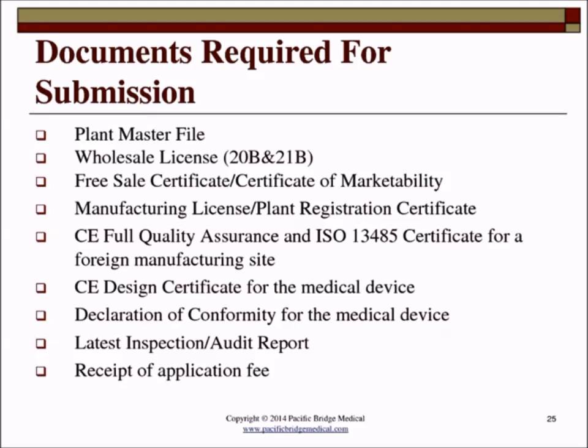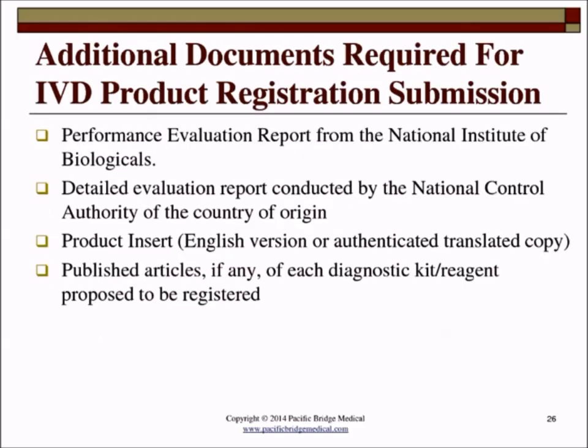Here again are some more things in the documents to be submitted. The following additional documents are required for notified diagnostic kits. Beyond what we said in the last couple of slides for devices, if you have diagnostic kits, you have to provide some additional information. Besides what's listed here, you may have to provide things like a specific batch test record for at least 3 consecutive batches, showing the specification of each testing parameter, from the manufacturer. Or you may have to provide a detailed test report of all the components used in the finished IVD kit. And while only 3 types of IVDs are notified and must go through product registration, as I mentioned earlier, all IVDs, including the non-notified IVDs, will need to get an import license to be sold in India.